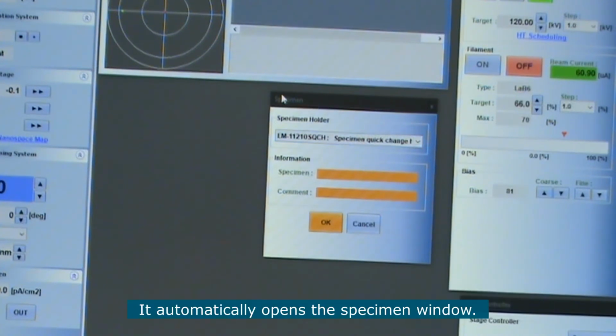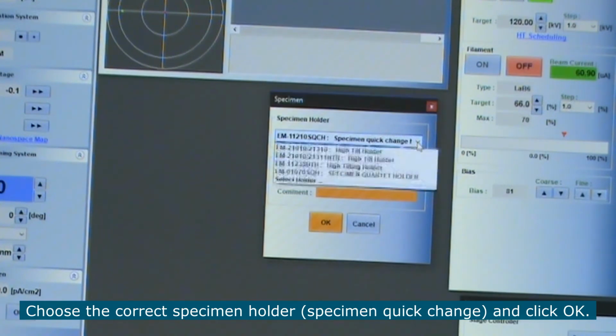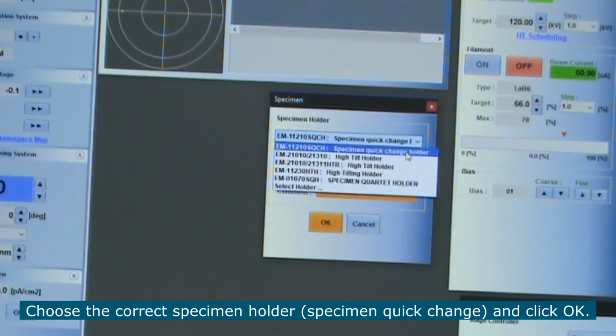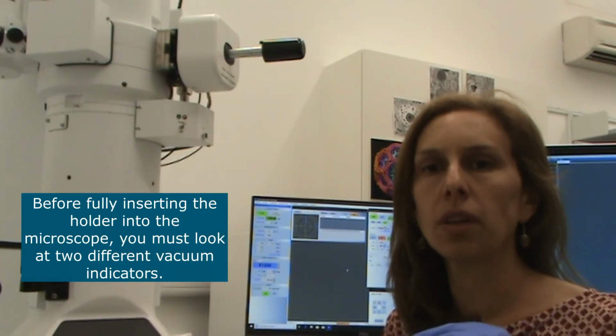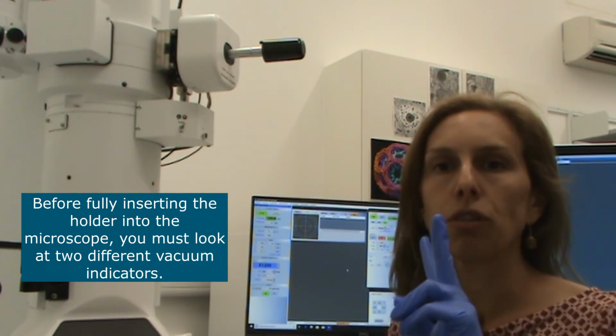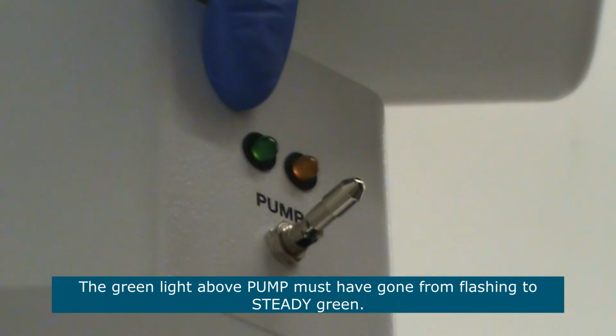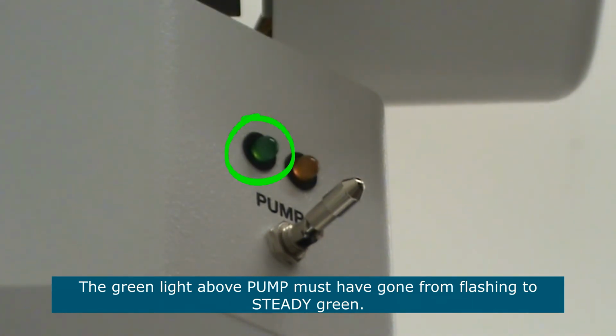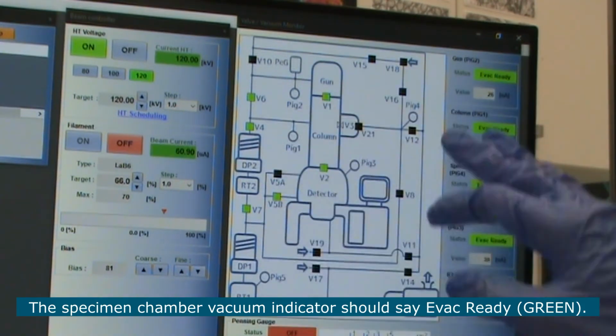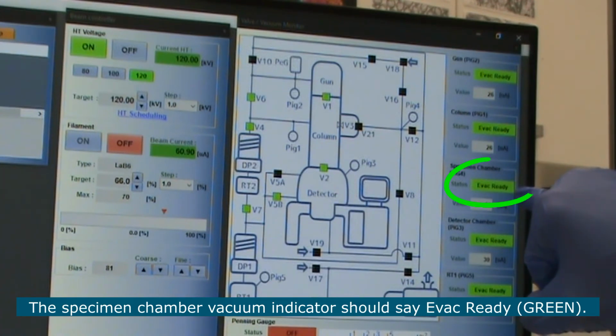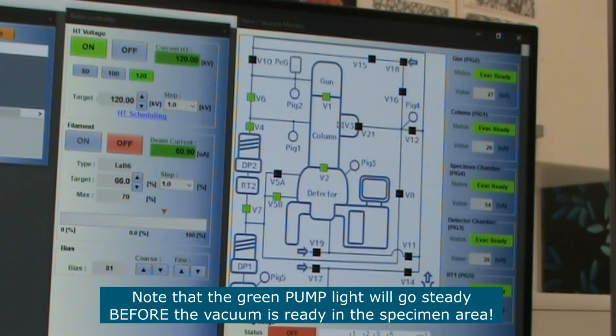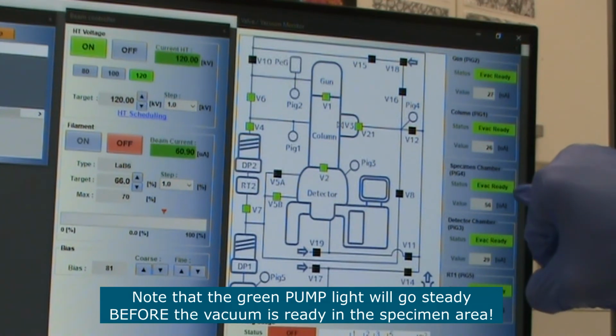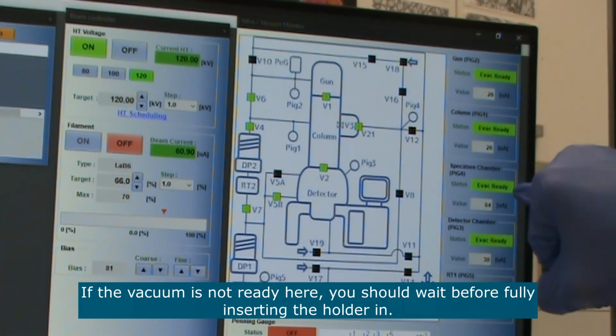When you start inserting the holder into the microscope and you tell the microscope to pump the specimen area, it automatically opens this window here. Here you should choose the right type of holder that you are using. Use the drop-down menu to choose Specimen Quick Change Holder and then click OK. Before fully inserting the holder into the microscope, you have to look at two different indicators. This green light here must have gone from flashing green to steady green. In the vacuum monitor, the specimen chamber vacuum should have gone from not ready to evac ready green. The green light in the air pump switch will go steady before the specimen chamber is ready. So if the vacuum is not ready here, you should still wait before you fully insert the holder into the microscope.